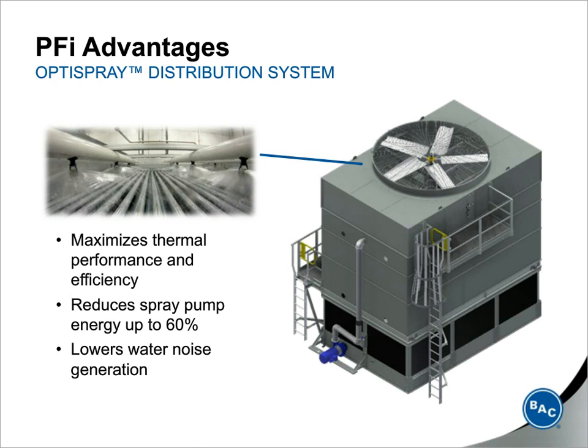There's another feature that I wanted to highlight of this new counterflow design that helps reduce energy consumption over traditional closed-circuit cooling towers, and that's the optimized spray distribution system. BAC actually calls it the OPTISPRAY distribution system. Now, by optimizing both the recirculating water flow, or the spray pattern, and the airflow, this design can achieve greater thermal performance than traditional designs, and it can actually do this with a smaller spray pump that can use up to 60% less energy. Now, since the spray pump runs throughout most of the year and it's always at full speed, this smaller pump size really minimizes the total unit energy that's used and reduces energy costs throughout the year, because the fan motor can actually be throttled by the VFD, whereas your pump is typically going to be running at full speed all year round.